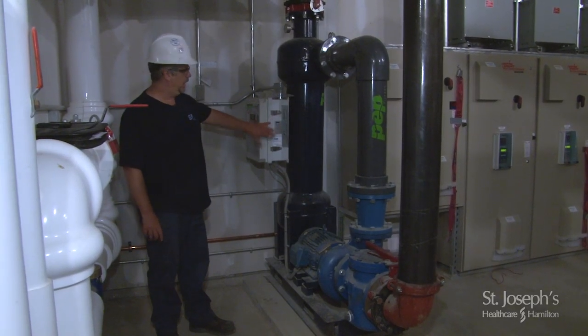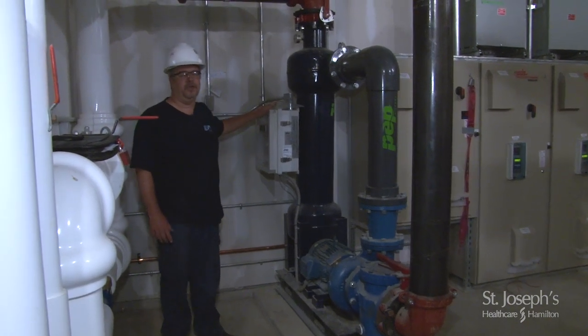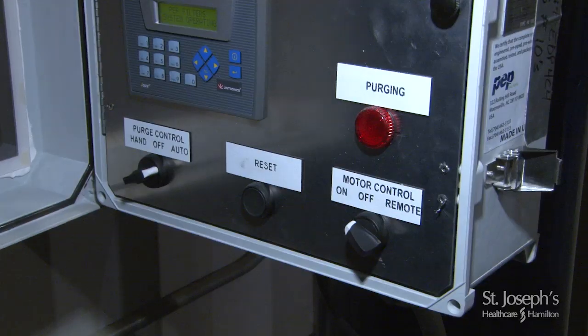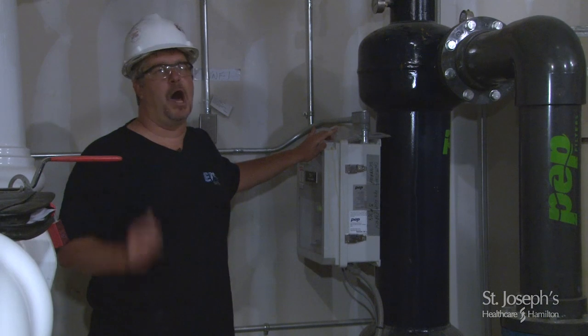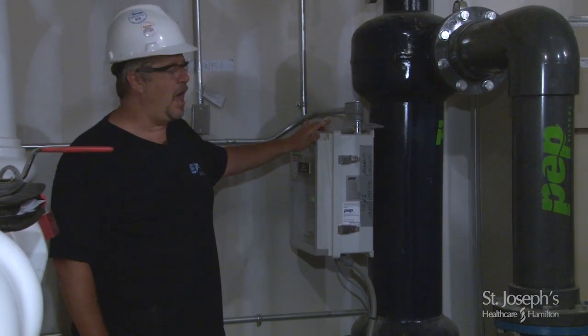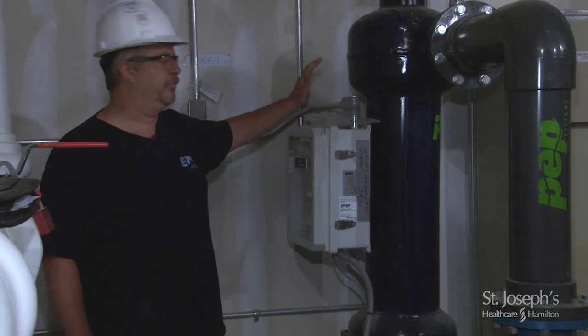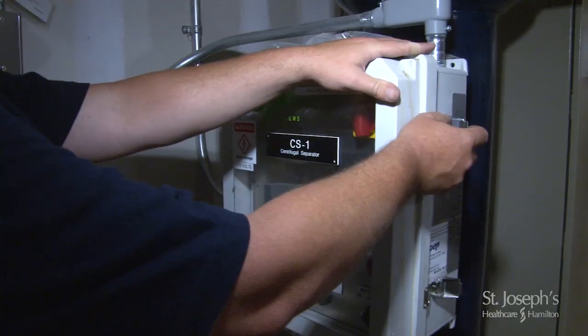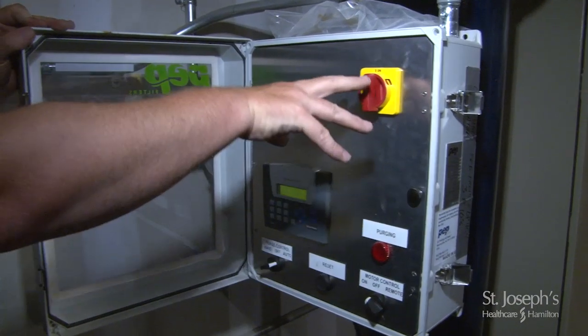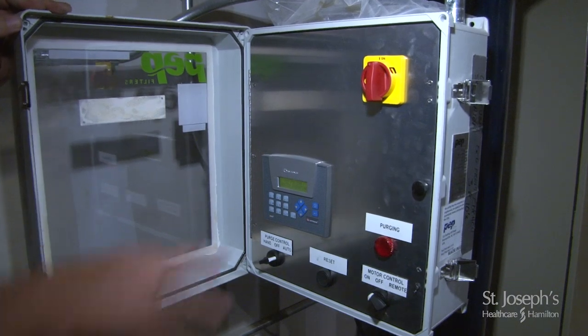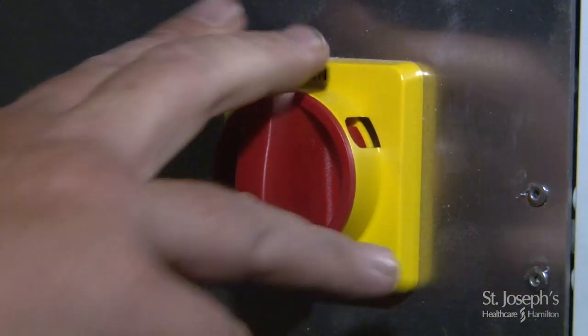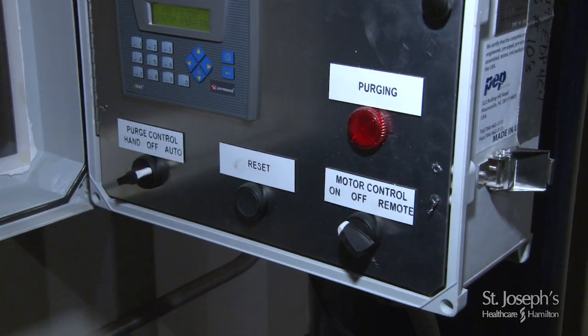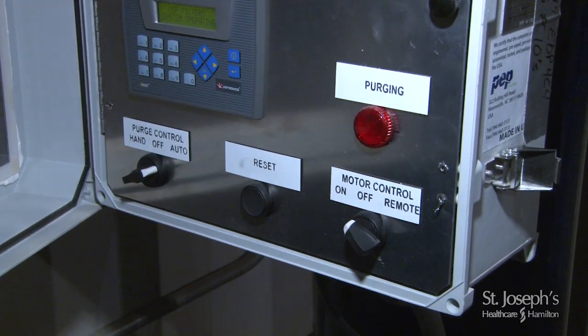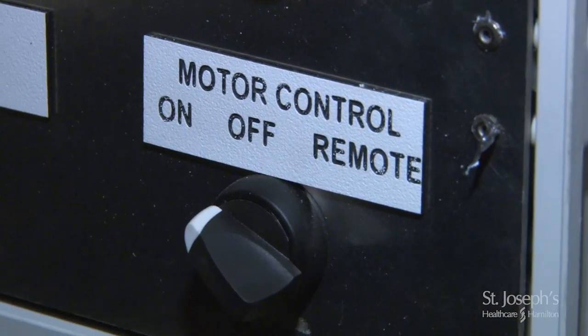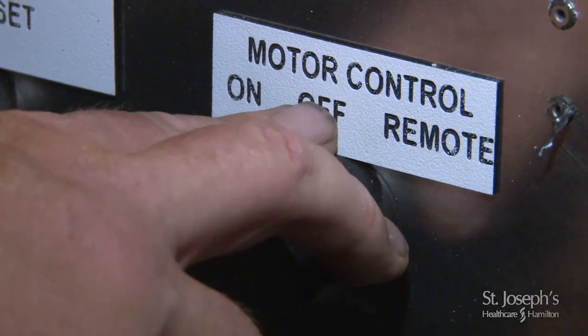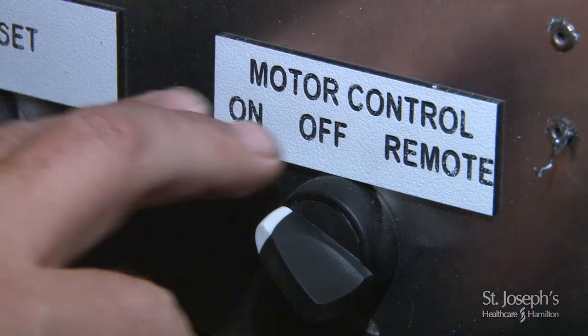On the side of this filter assembly is the control panel. Internally, within this control panel, there really are no serviceable items. There are some switches that the operator needs to turn on or off depending on what operation you want the unit in. Other than that, for any failures within this box, a representative of the manufacturer needs to be contacted for service. Inside this box, you have your main power switch. It's either on or off. When the towers are in operation, this should always be in the on position so that we ensure we're filtering the water properly. Down below you also have a motor control, off and on. There is an area where you can hook it up to a remote sending system. This unit in particular hasn't been set up for remote, so we're only concerned whether the motor is on or off. Once again, when the tower is in operation, it should always be in the on position.